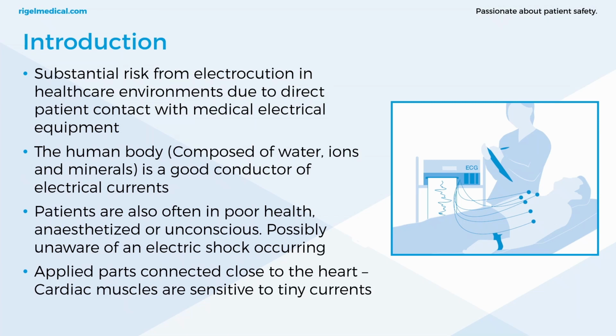Okay, so starting from the beginning, where electrical safety was implemented, where the risks from medical devices occur for patients. When an individual comes into contact with any type of faulty electrical equipment, there is always a potential risk for electric shock. The cardiac functions, the nervous systems, the muscular systems, they're all sensitive to the effects of electrical current passing through the body. And this is especially true at the commercial frequencies of electricity, 50 or 60 hertz worldwide.